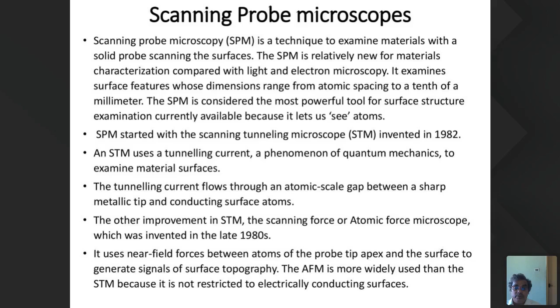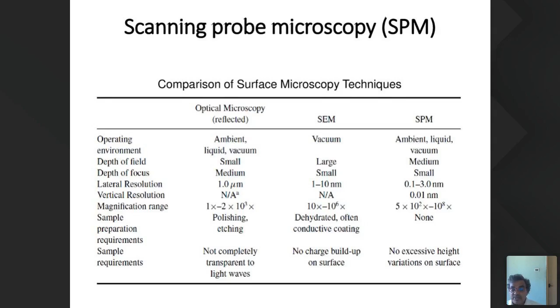If you compare the electron microscope and the scanning probe microscope, the electron microscope mostly needs a vacuum atmosphere, whereas SPM is not like that. You don't need a vacuum; ambient conditions are also possible. The resolution is very high: 0.1 nanometer lateral resolution is possible. The vertical resolution is 0.01 nanometer. That means it is very good for atomic resolution, even less than the atom's size. No excessive height variations on the surface should occur in the scanning probe and tunneling microscope.